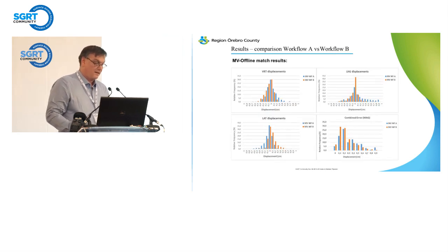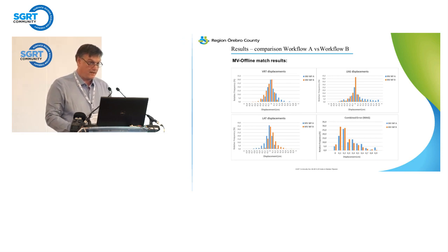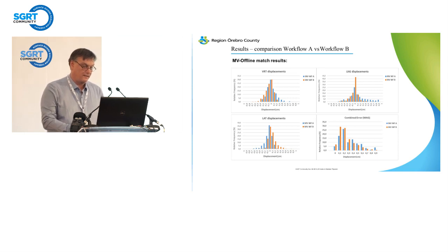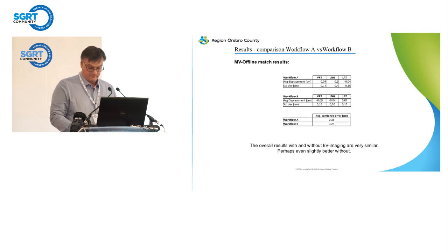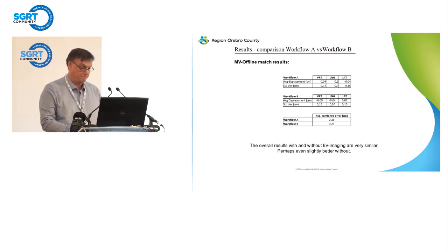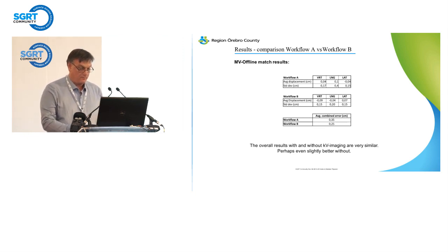The results look something like this. We have the vertical displacements, longitudinal displacements, lateral displacements, and the combined magnitude. Looking at the distributions, they look rather similar. For workflow B, the spread is within limits we consider quite acceptable for tangential breast treatments — within two to three millimeters for most of the results. In tabular format, the overall results with and without KV imaging are quite similar. We could even say it is slightly better without KV imaging — the combined magnitude error is somewhat lower in workflow B.